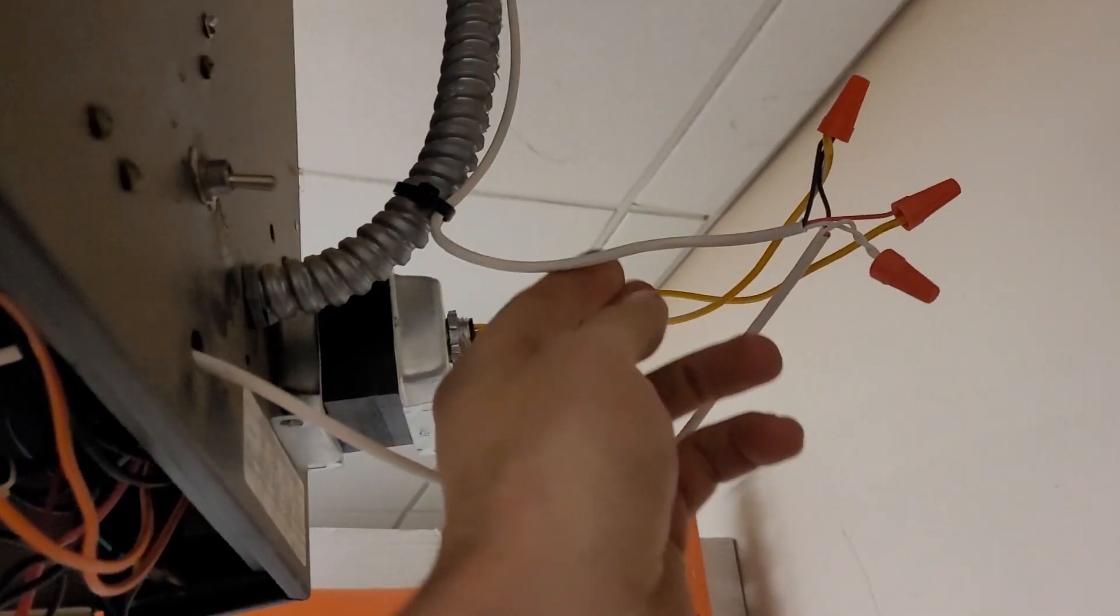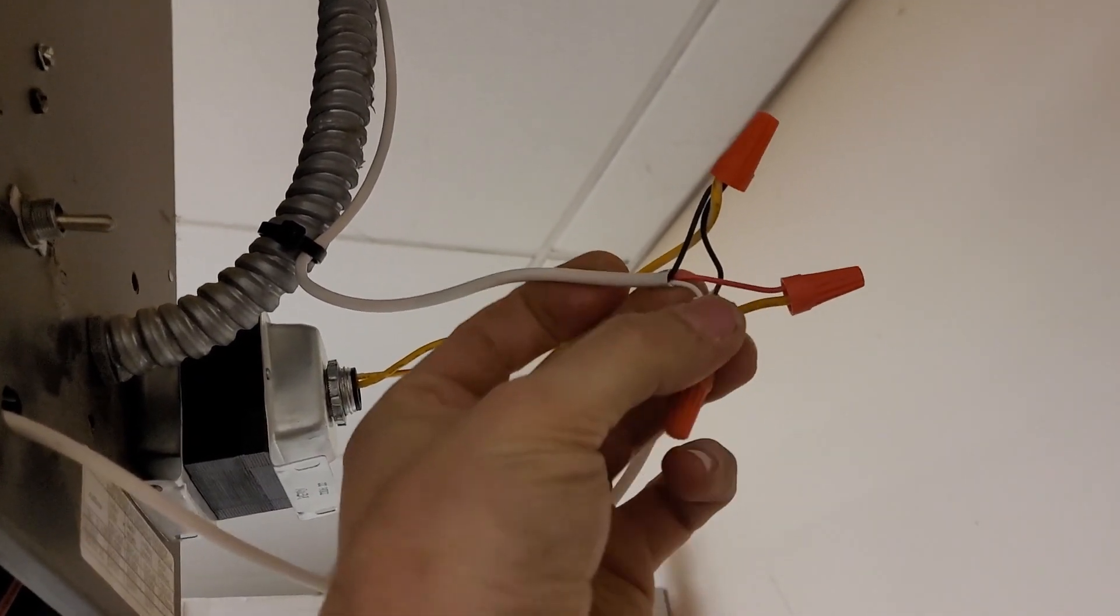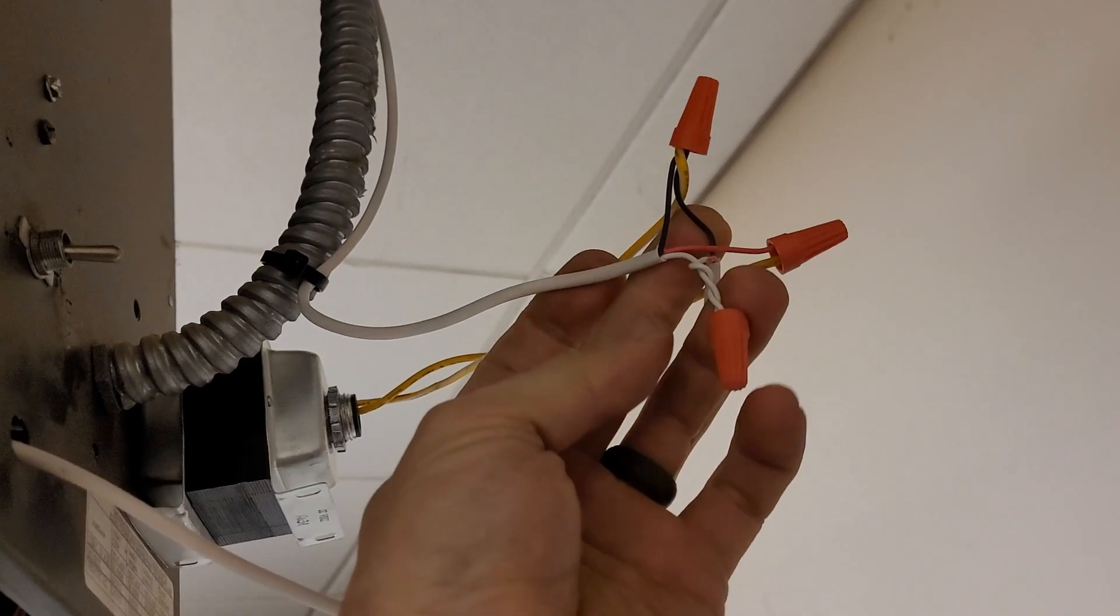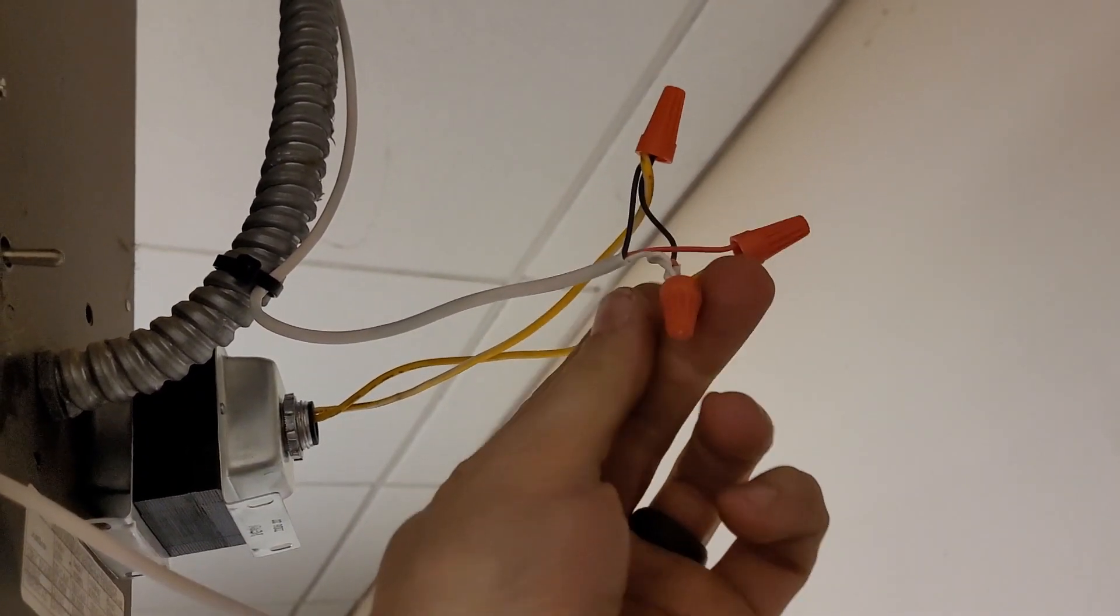The 24 volts is gonna get sent over to the thermostat. There's three wires going to the thermostat - red and black for power and common coming off of that transformer, and then white coming back from W1 or the heat call.